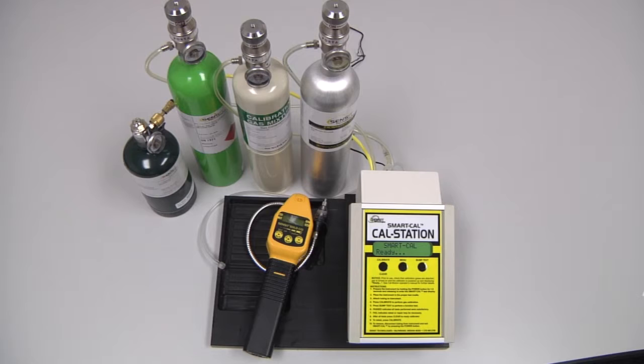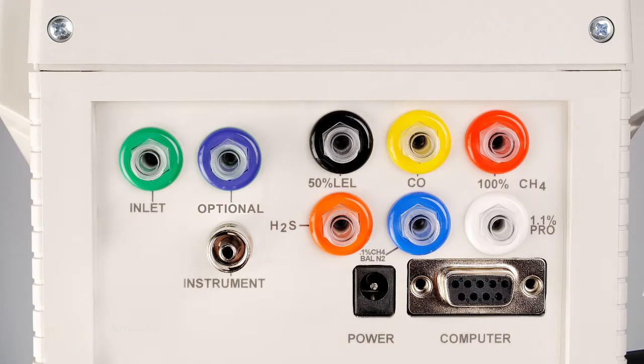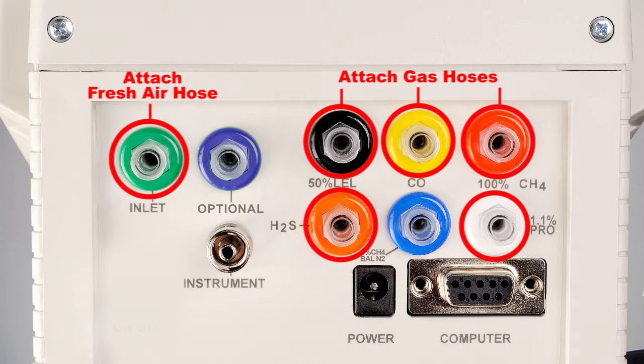This is a four gas instrument set up for natural gas, so we will need a combination bottle of 50% LEL methane and 100 ppm carbon monoxide attached to both the black and yellow inlet of the cal station through a Y adapter, a bottle of 25 ppm hydrogen sulfide attached to the orange inlet, a bottle of 100% by volume methane attached to the red inlet. If this instrument were set up for propane, we would need a bottle of 50% LEL propane attached to the white inlet.